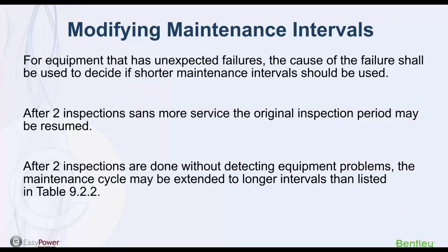You can modify maintenance intervals, as mentioned. Certainly, if you're making it more frequent because of conditions, that's what you need to do. But it even gives you language about how you can extend the period between maintenance. If you're doing your maintenance, checking your equipment, and never finding anything wrong, potentially you can lengthen the time between maintenance schedules, and the document does discuss that to some degree.